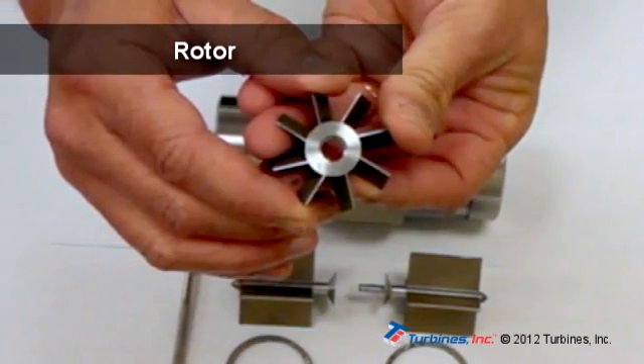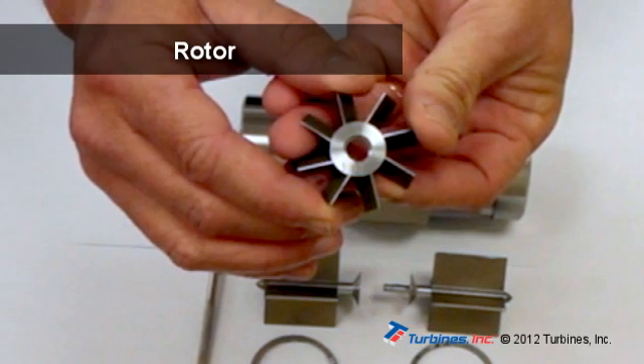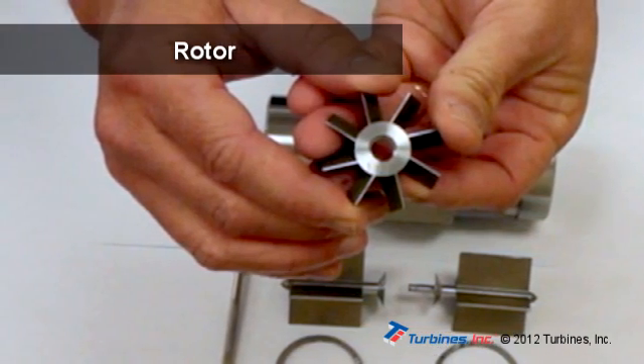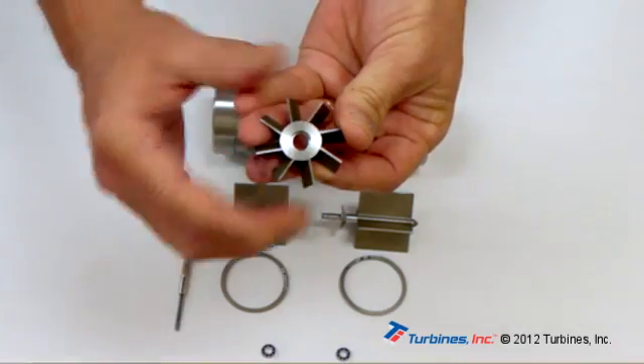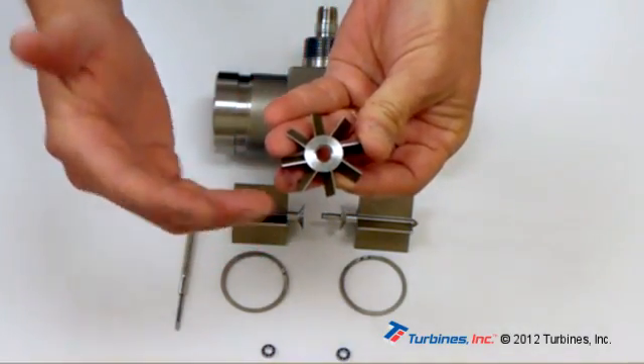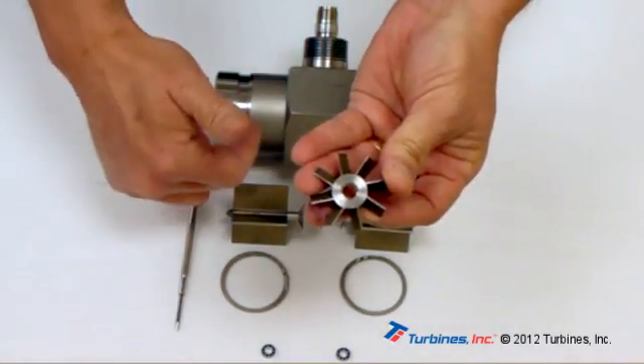Next we will move on to the rotor. The rotor is 17-4 stainless steel. You will notice that it has an N etched on it and that is the way the flow meter was calibrated. We need to make sure that we assemble the rotor appropriately with an N etched on the housing as well.